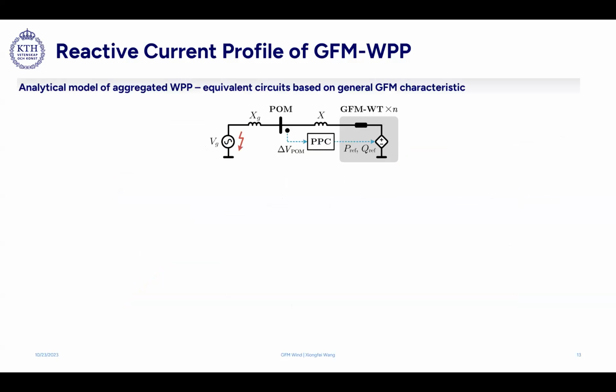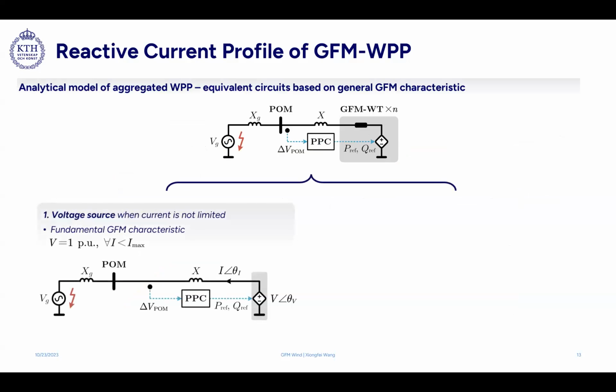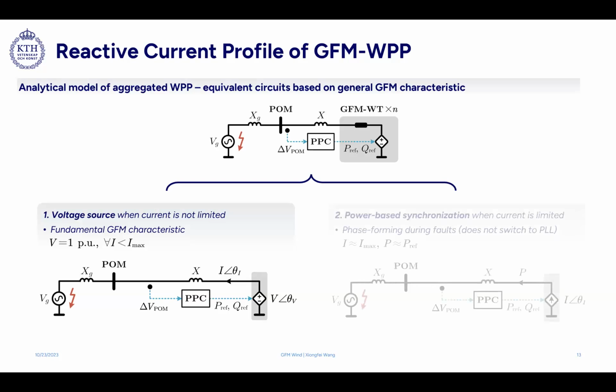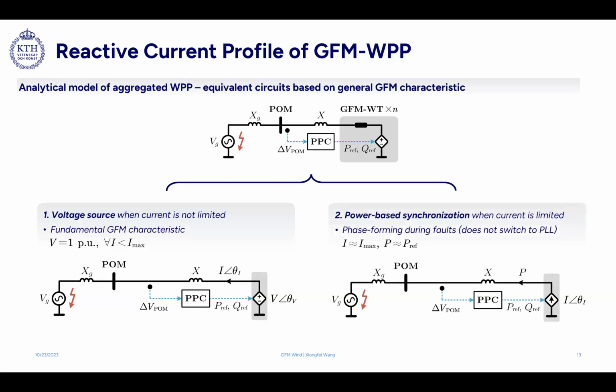So in this study, we try to build an aggregated wind power plant model, based on measurements at the point of coupling of the wind turbines. In this case, we can have two different behaviors. One is without triggering the current limit: the aggregated wind power plant can behave like a voltage source. Then the fault current or the reactive current really depends on the output impedance, or the internal voltage source and the PCC. The second case is if we trigger the current limit, how do we do the synchronization?